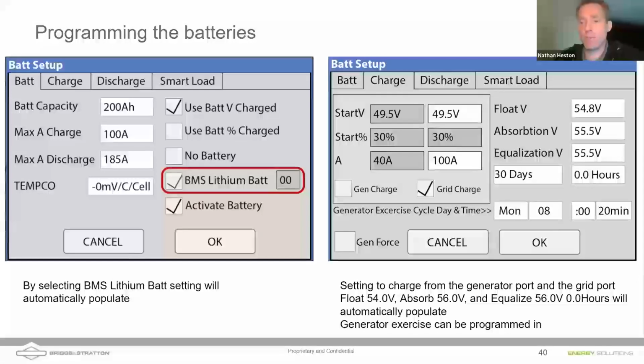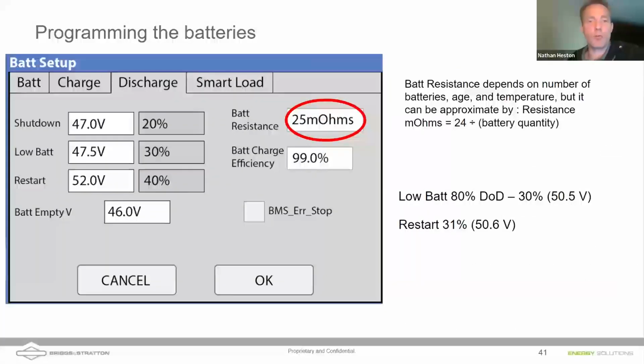That equalization there is for burning off sulfur for lead acid batteries. You never want to use that with lithium batteries. Let's jump into the discharge cycle. So the battery resistance, for our batteries, has to do with the drop in the voltage output of a battery that depends on loads. So if you notice your battery bank getting below your LBCO, where the inverter is still running, it's because there's some compensation with this setting. So if you can't get below your LBCO when you have large loads, or if your inverter is shutting off a little too early, make sure you have the appropriate battery resistance programmed in under this tab.